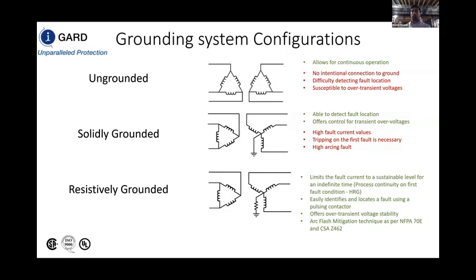That allows them to eliminate transient overvoltage conditions by shorting out the capacitance that exists between conductors and ground. The only issue is that when we detect a fault, although we can locate it very easily, we have to trip the fault right away because otherwise there would be circulating fault currents going back to the source in the magnitude of thousands of amps or more. And that could cause an arcing condition, which is problematic. So in the case of a solidly grounded system, you're reducing the transient overvoltages, yes, but you're compromising process continuity as a result.